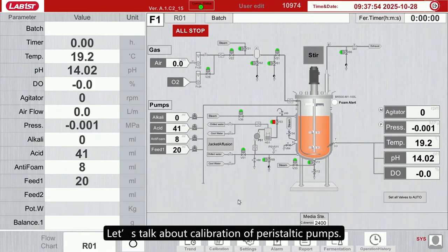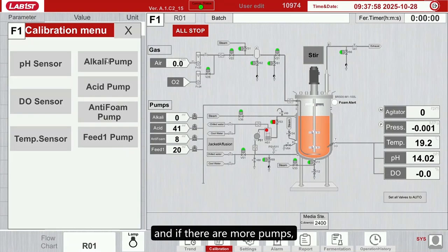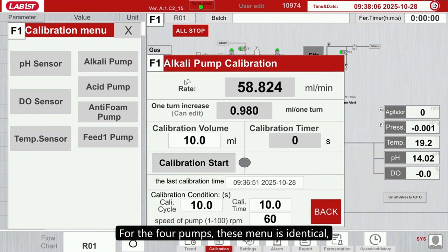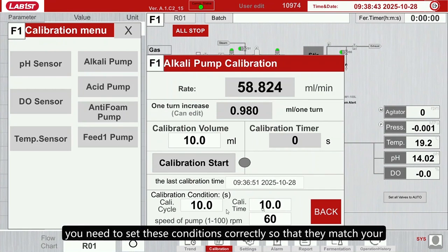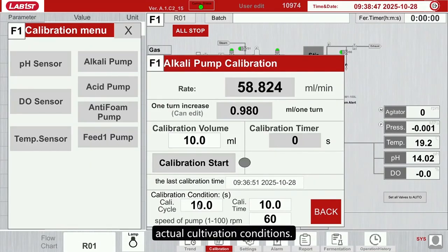Let's talk about calibration of peristaltic pumps. The standard configuration includes 4 pumps, and if there are more pumps, their calibration will be displayed below. For the 4 pumps, the menu is identical, showing rate and 1 turn increase, which means the volume in milliliters per revolution. Then here is the calibration volume, with start and stop buttons for calibration. And below the last calibration time, there are the calibration conditions. Because the peristaltic pump operates in pulses, to enhance precision you need to set these conditions correctly so that they match your actual cultivation conditions. This way, calibration will be more accurate.